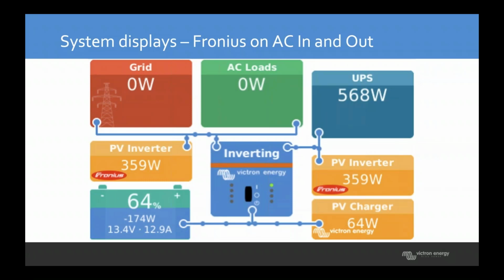Here's another example, this time with two Fronius inverters connected. In this demo they're the same power output, but let's say there's two: one on the AC input - you can see it's connected via the blue line to the grid side, but the Victron system can still see it, so I can still use it for charging or running loads - and one connected to the output side, so it'll survive if there's a grid outage, whereas the one on the left-hand side will also be disconnected in that case.